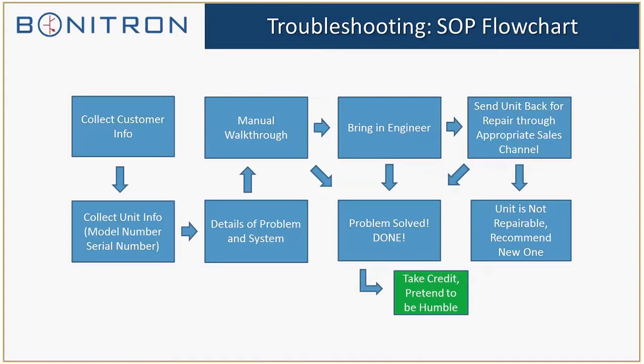So this is a quick, basically standard operating procedure for when I get a tech support call. First off, I collect their info, just to understand who I'm talking to. Is it the end user? Is it a distributor? That lets me know the priority level, how much the customer's down, or what sort of situation it is. I collect info about the unit, details of the problem and system. Then I either walk them through the manual or use my experience. Hopefully the goal is getting them up and running as quickly as possible, whether it's a new installation or something that stopped working. Or if worst comes to worst, get the unit repaired or recommend a replacement.